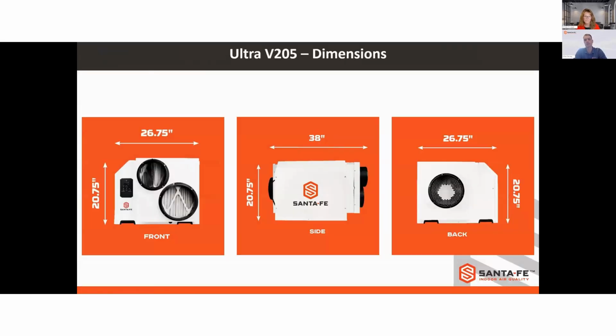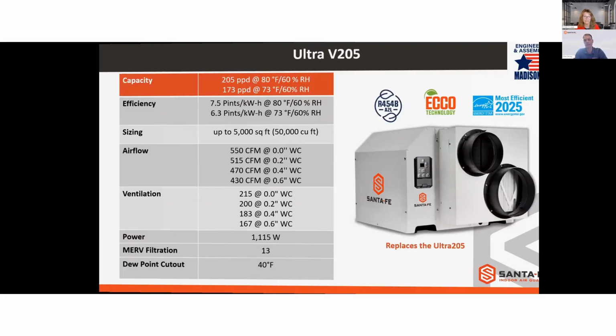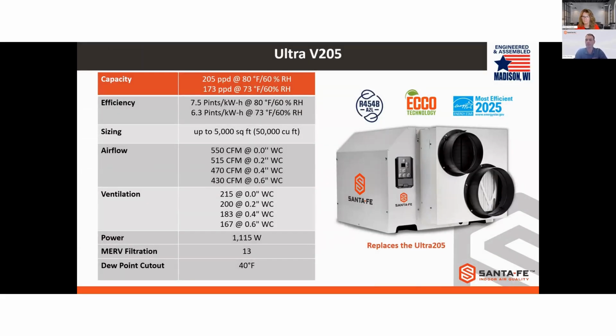Nikki, I was just going to add on that one. We're talking about efficiency and all these things. The reason this particular unit is quite important is if you look at the power consumption, it's about 1,100 watts. That's capable of being installed on a dedicated 15 amp circuit, which really makes this quite impressive. All the units you've talked about so far, a dedicated 15 amp circuit is more than enough. Yep. Perfect. Thank you.